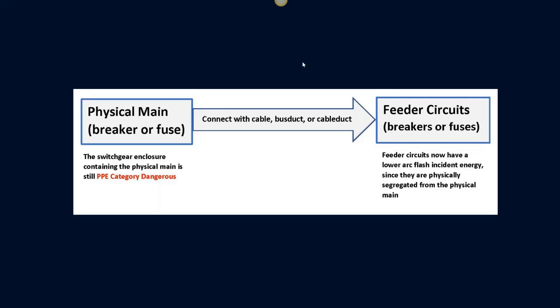So in this picture here, we could see from an arc flash mitigation point of view, if we don't want to use a secondary virtual main, if we have a physical main, our only choice, and not to make the entire lineup PPE category dangerous, meaning typically over 40 calories per centimeter squared, meaning no personal protective equipment is safe, is to physically segregate the feeder circuit from the main. And we can do that and connect with conduit, bus duct, or cable duct. But that's going in the exact opposite direction of Michael McClellan's excellent presentation today of how to save real estate in the electrical room, and particularly in new construction, real estate is very expensive.